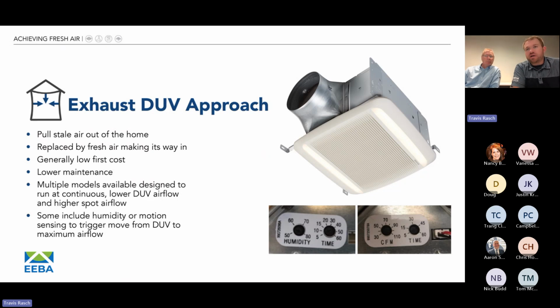So again, we're having a dedicated exhaust fan. Typically, like Pat mentioned, it has some requirements as relates to zones, as well as the CFM that's being delivered. Again, this is typically put in a place and or can be piggybacked on another bath fan within the house. But again, its job is for the whole home mechanical ventilation. And you can see here there are some different options as relates to models and various features which you can include with this type of product, being both humidity as well as a timer control, as well as CFM. So as Pat mentioned, you have that table, you have that calculation that's being done. These particular models can offer that full range so that you can dial in that CFM that you're requiring based on that calculation or that table that Pat had shown earlier.